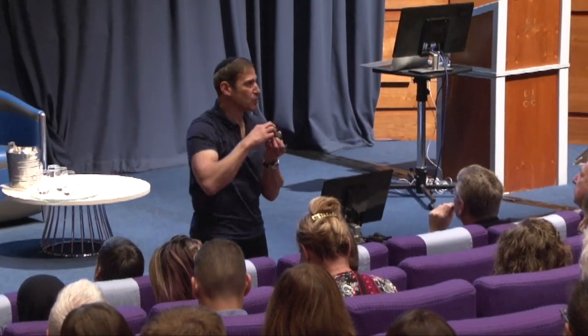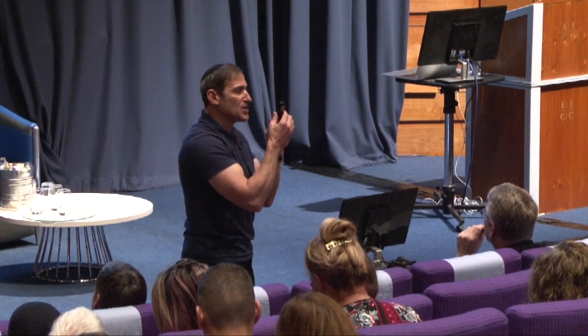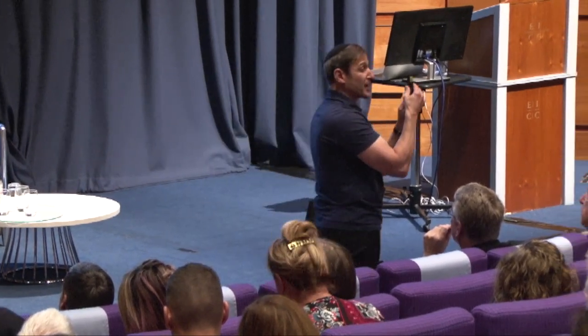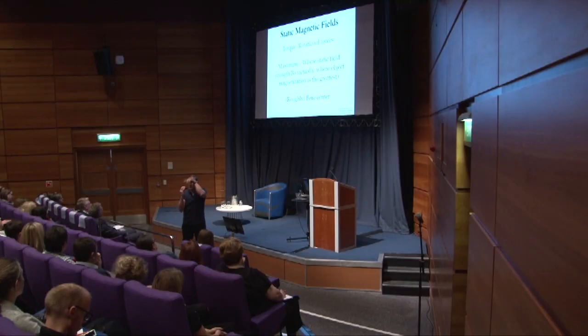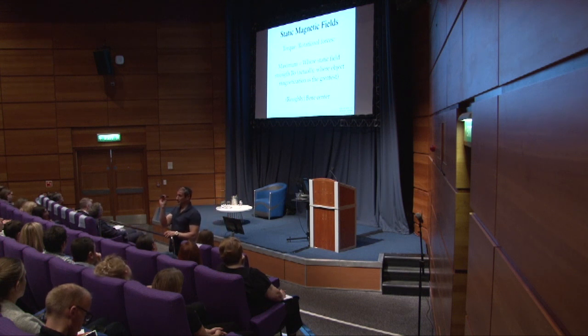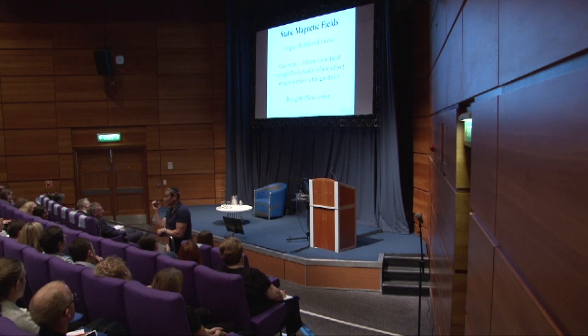You know those diagrams they show of a bar magnet with lines going around? Take that piece of metal: if it has a long axis, it's not going to cross those lines of force going this way, it's going to try to line up parallel to them, wherever it is. So if it's in the field, it'll line up north-south. And the stronger the field, the more it lines up, with greater strength to keep it that way. You try to turn it, it'll flip back with greater strength, the stronger the field. So wherever the field is strongest, torque is strongest.